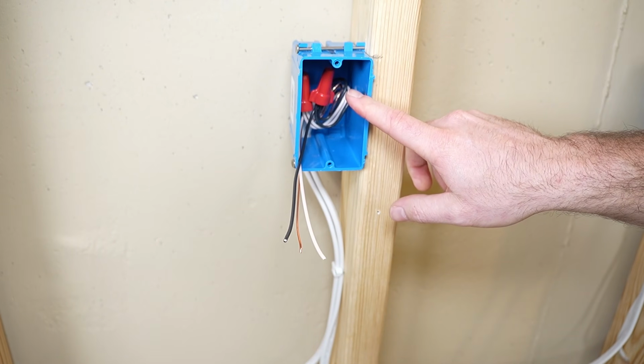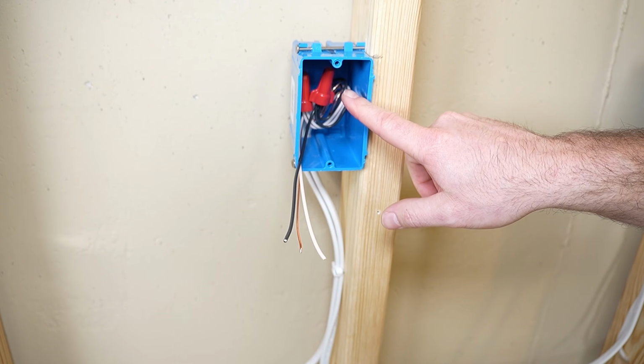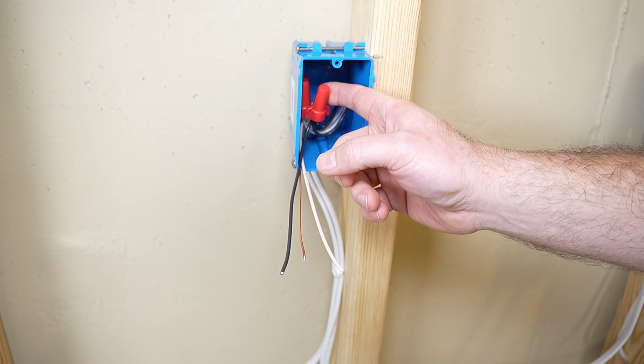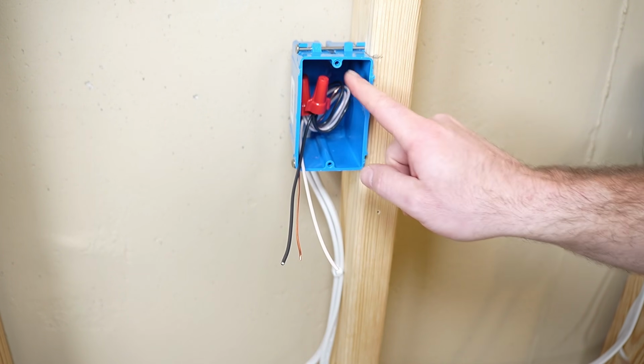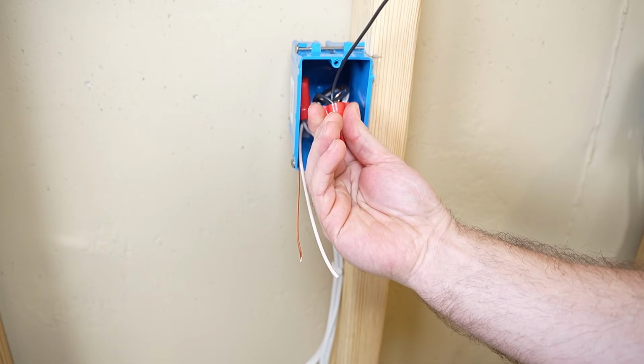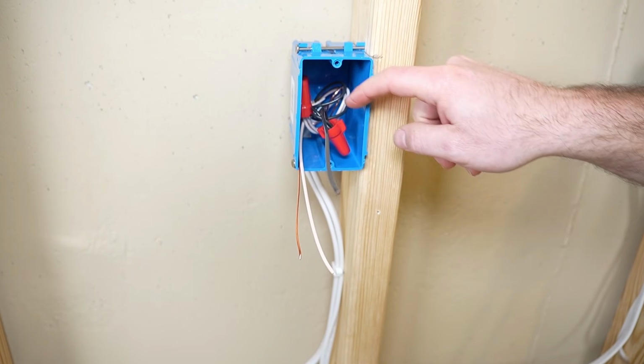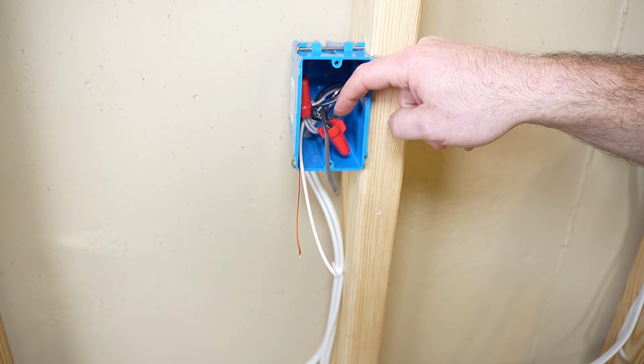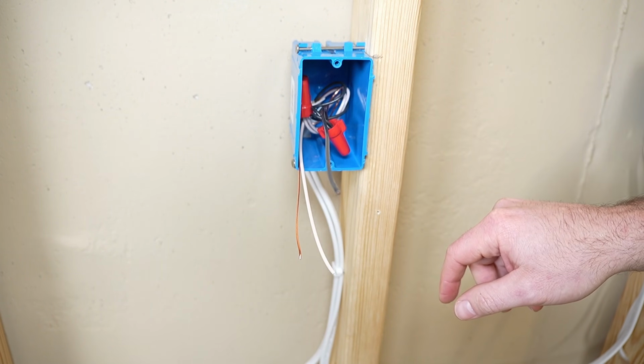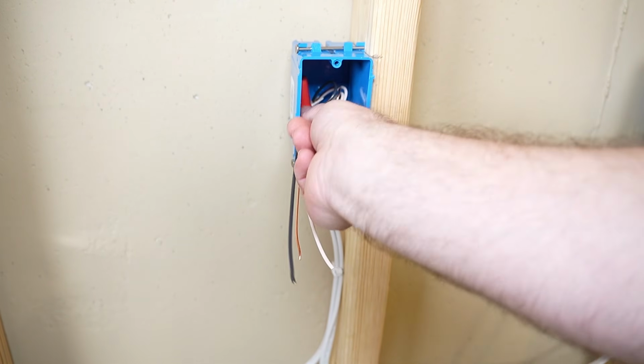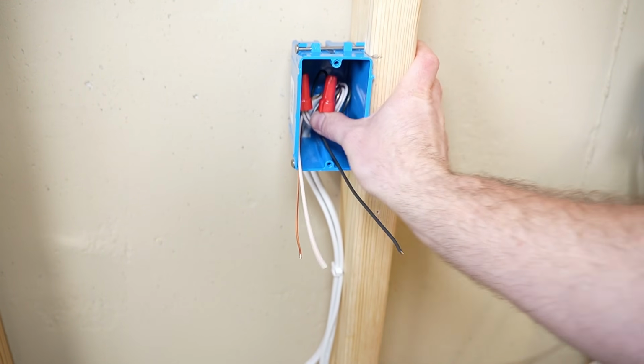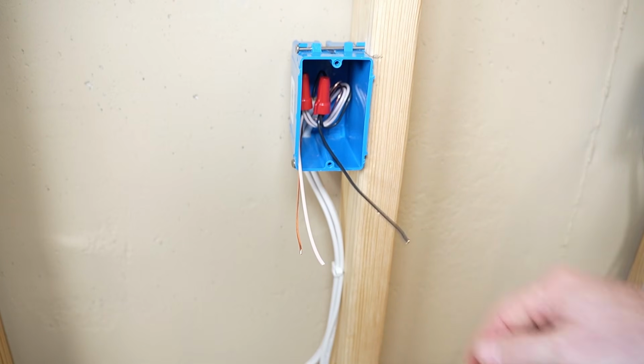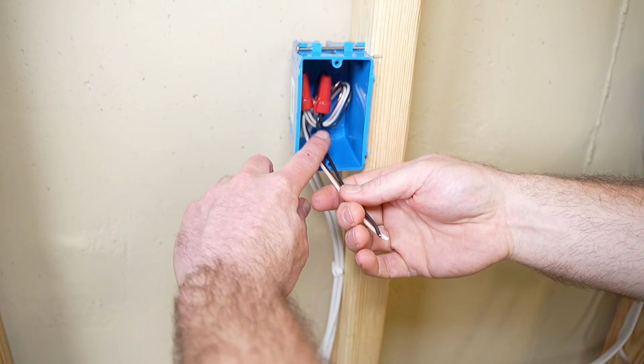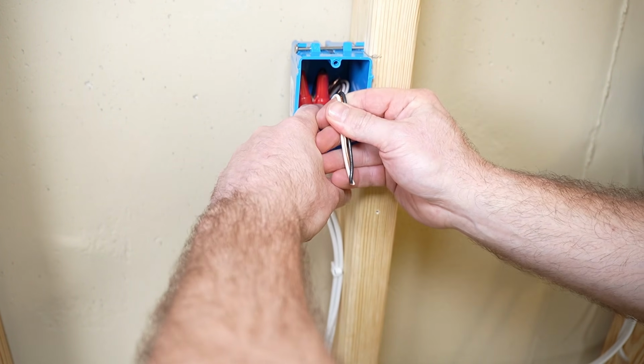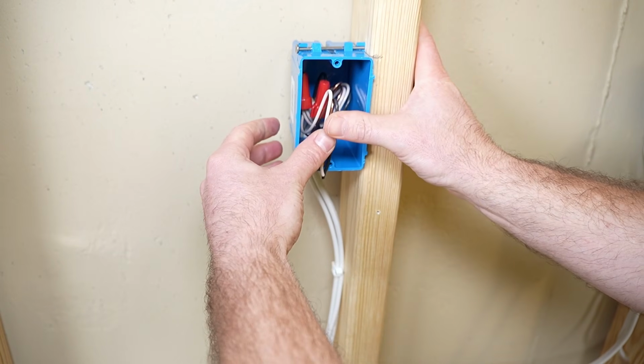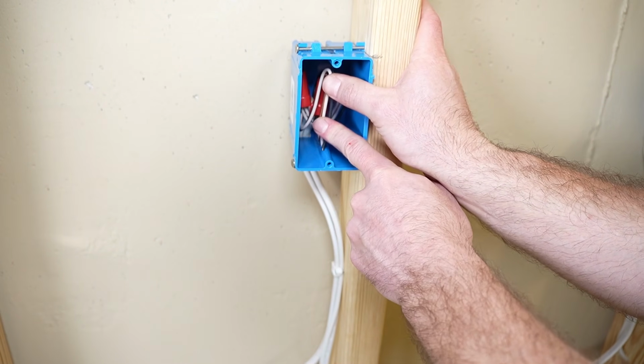I mentioned in the wire nut video that wire nuts are hats, not buckets. So we want to make sure our wire nuts are facing upwards. We do not want our wire nuts to be upside down in the box because moisture and debris can actually find its way into the wire nut and cause premature failure of that splice. So wire nuts are hats, not buckets. Make sure they are facing upwards. So with this splice shoved in the back of the box, now we can pull our pigtails to the front of the box and leave them bundled together like so.